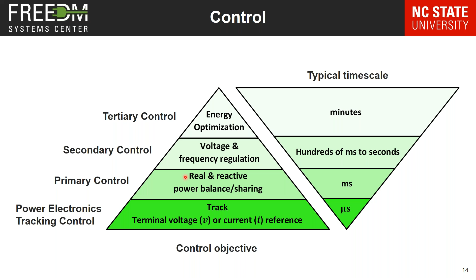And even though they may be able to receive power, if they're not receiving those commands from the controller, they wouldn't operate properly. So you would have to design in within the control system the resiliency of - okay, we're operating islanded, or we're operating grid connected - what happens if I lose communications? So these are the pieces you need to manage. Most people have taken centralized control as their approach, but there's a different approach, and you can use a decentralized control approach.